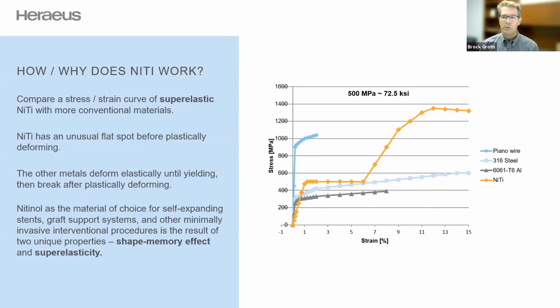These other materials are aluminum, steel, and a different type of steel piano wire. I won't get into how close the aluminum curve is to steel's. For all these materials, particularly nitinol, these forces can be adjusted by how the material is processed, but it's the drastic shape of these curves I want to highlight. Nitinol starts with a linear elastic phase, same as steel, but then has a flat loading plateau where you get a lot of movement without a force increase, and then it continues from there and ultimately permanently deforms and breaks.